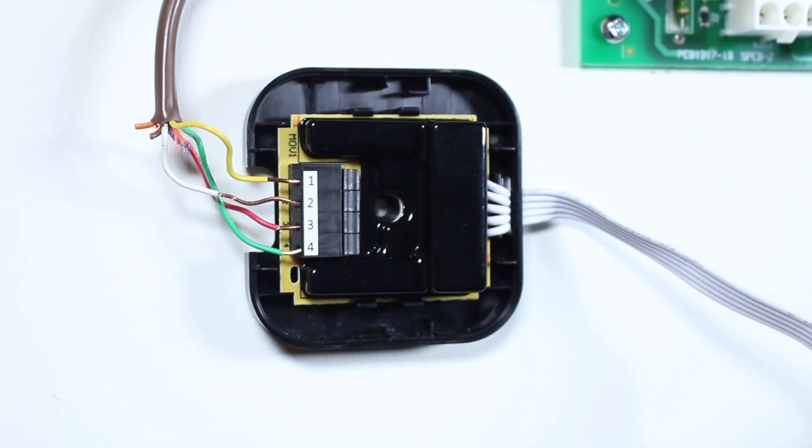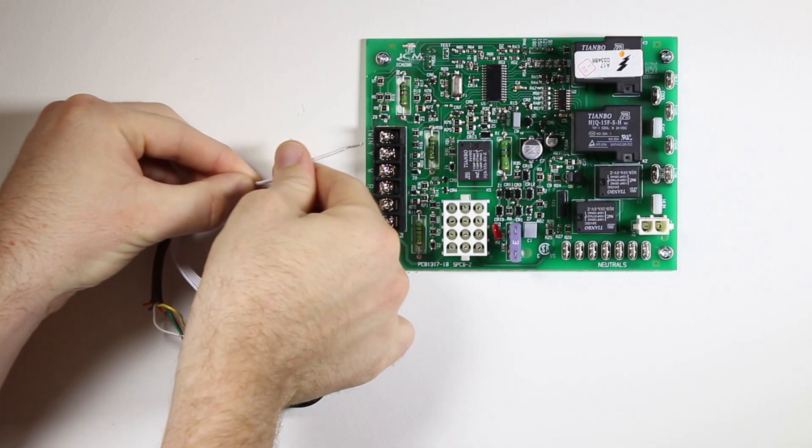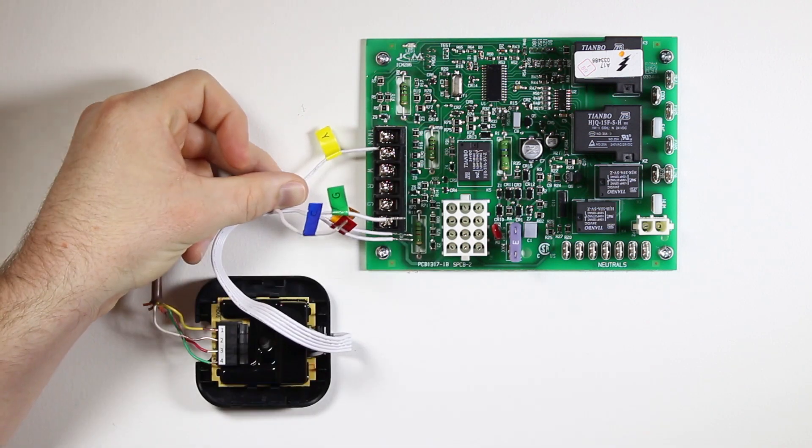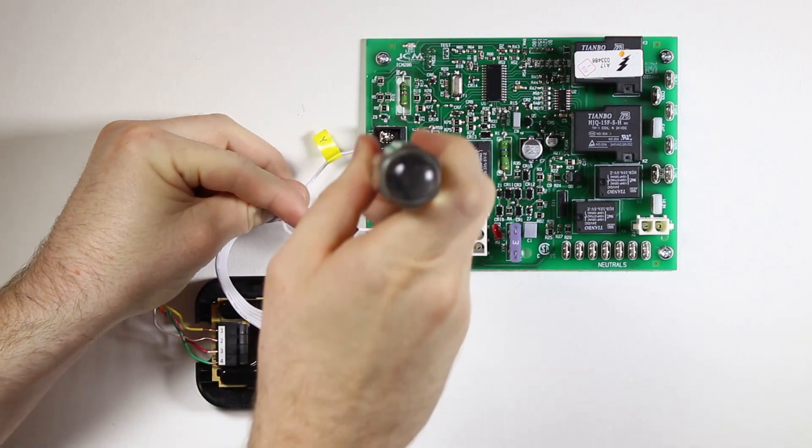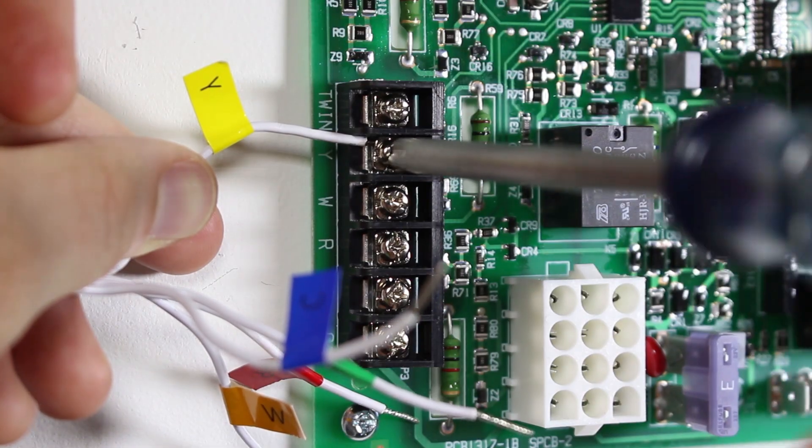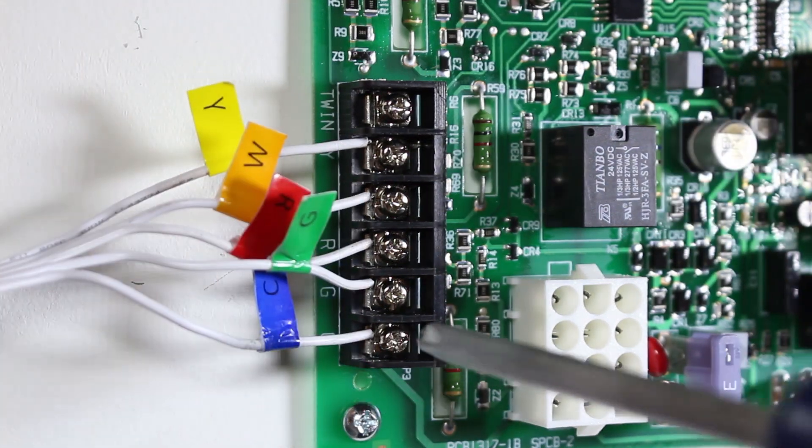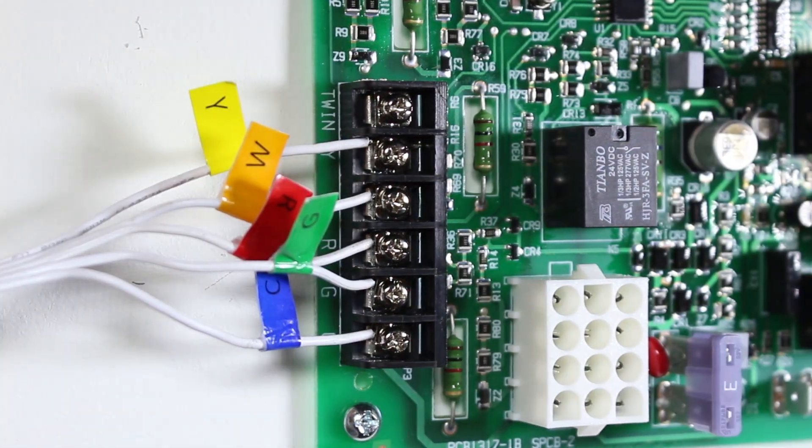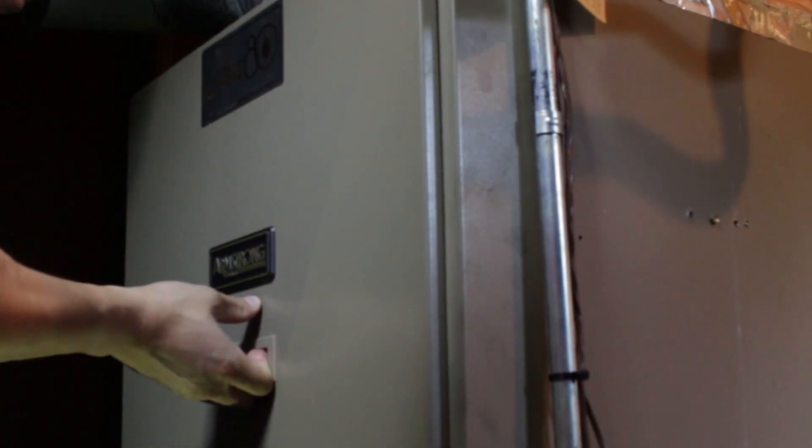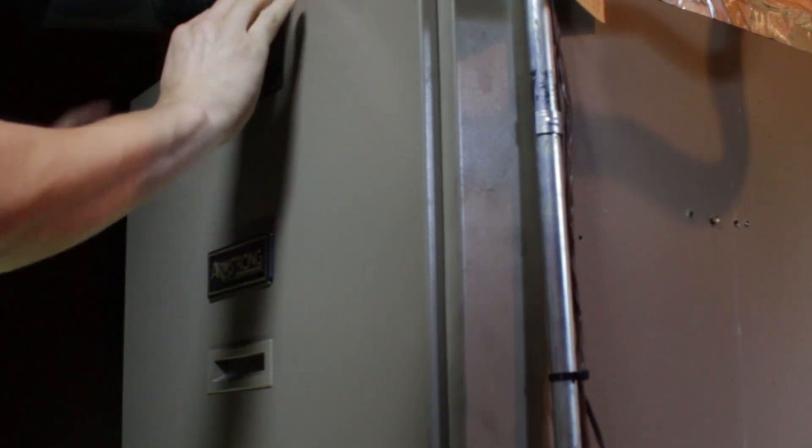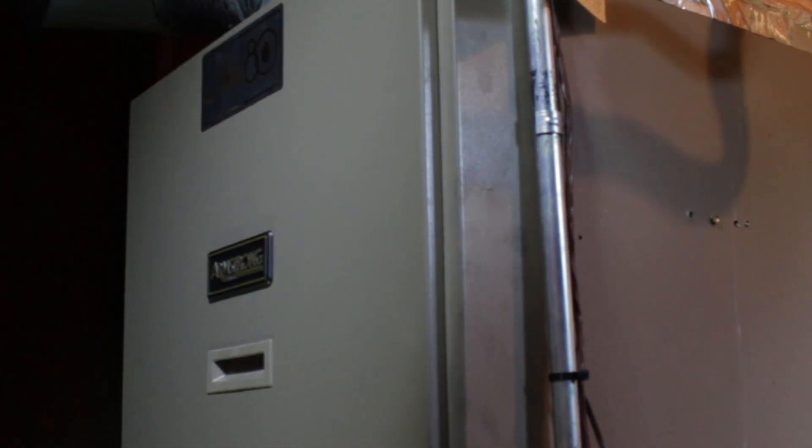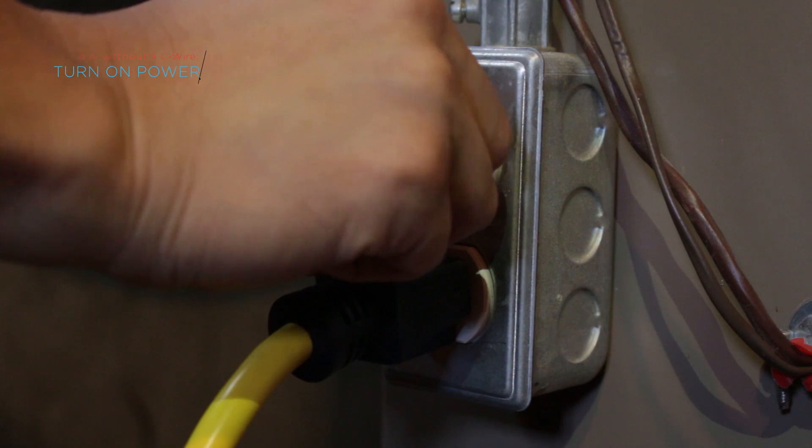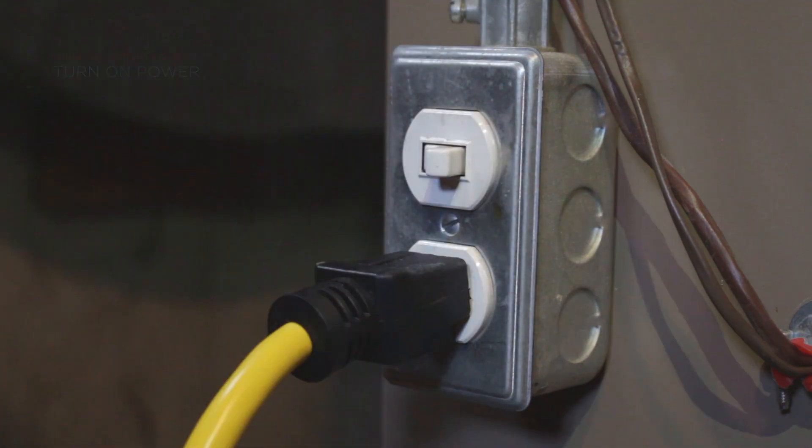insert the wires coming out from the power bridge into the corresponding terminals on your furnace control board. You will now have a wire going into the C terminal on your furnace. Secure the power bridge to your furnace and put your panel door back on. Return the power back on to your heating and cooling system.